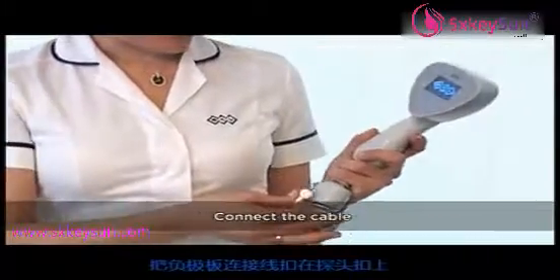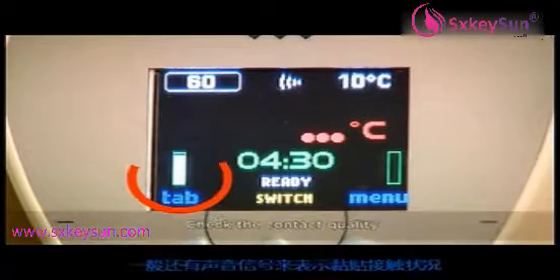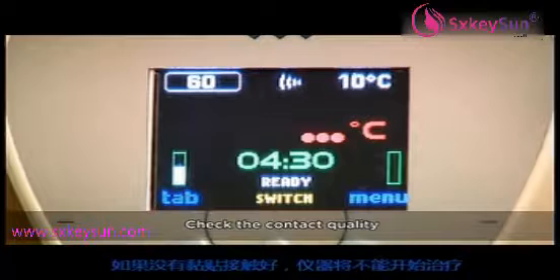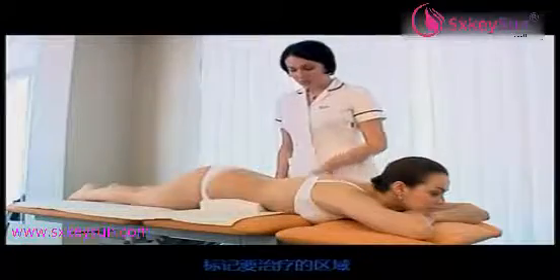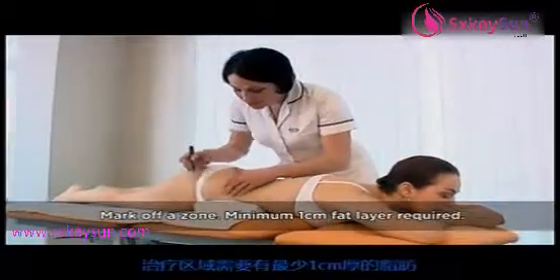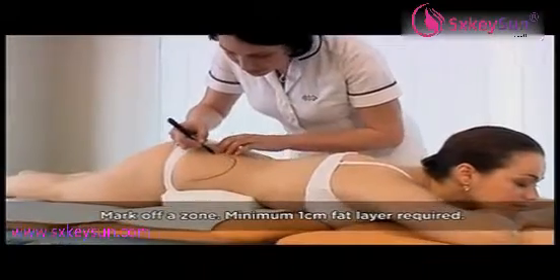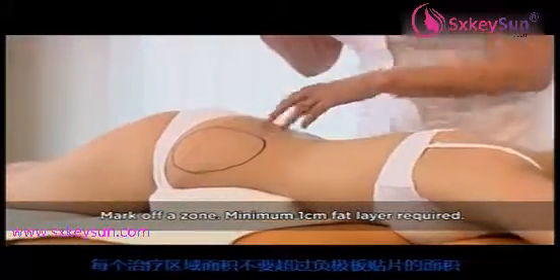Connect the electrode cable to the device. Check the contact quality on the applicator screen. Poor contact is also indicated by an audio signal. The therapy will not start if sufficient contact is not established. Mark off a zone to be treated. A minimum of a one centimeter fat layer is required in the whole zone. The size of each zone should not exceed the size of the reference electrode. Do not treat more than six zones in a single session.